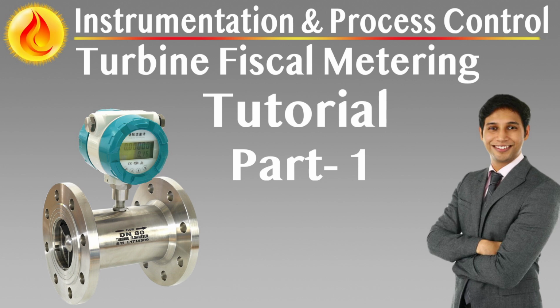Process isolation and safety provisions. Each instrument must be isolatable via block valves with vent and drain ports to allow safe maintenance without depressurizing the entire header. These valves must be installed in compliance with piping class specifications and allow zero leakage isolation. For systems handling volatile or hazardous fluids, thermal relief valves and hazardous drains must be included to protect against trapped pressure or accidental overtemperature conditions.